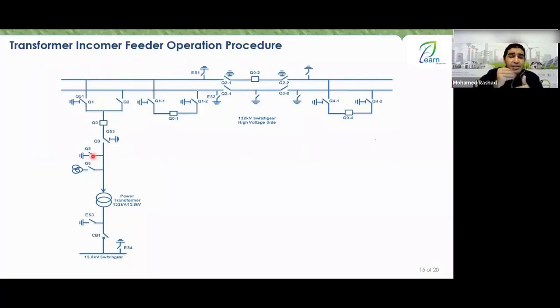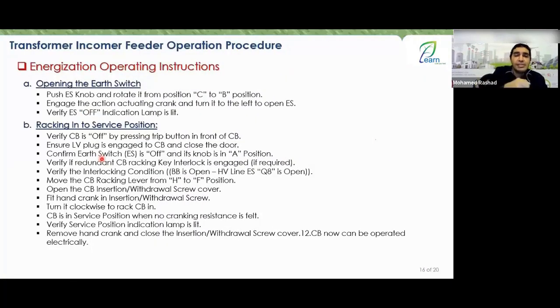The rack in and rack out movement for the circuit breaker relies mechanically on its ground and electrically on the external ground, and depends electrically on the upstream ground of my feeder. All right, you will move it from H to F. Insert the handle carefully until you insert the breaker rack in, ensuring the breaker is in the rack in position. You close the electrical switch and you have no issues.